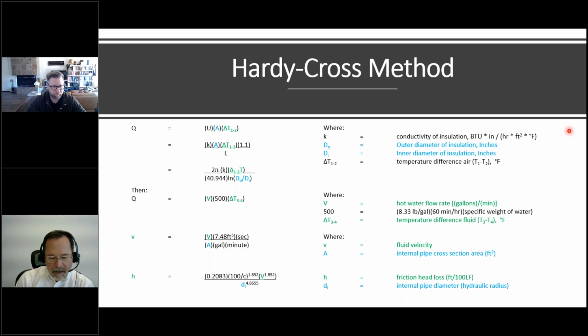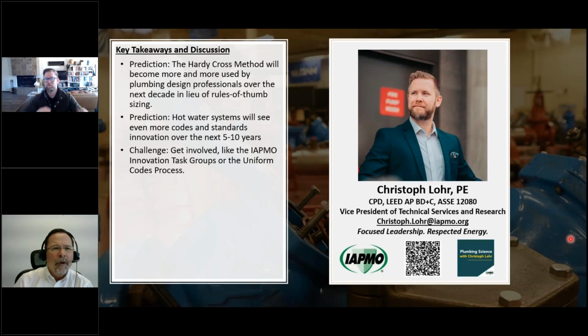So brand names anyways. I had a question for you, Christoph. In terms of balancing and a balancing contractor creating a balancing report for the client, we know that if they're using manual balancing valves, they can use their differential pressure tool and generate a balancing report and write down all the pressure drops and the GPMs. Is it a problem with thermostatic balancing valves that you don't test them? I mean, you don't have the ability to hook a differential pressure tool up to those.